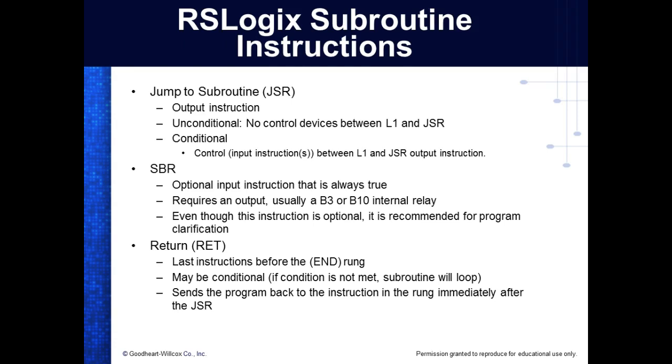Well, if I can't put something up at the very top that says this is an interrupt subroutine or this is a standard subroutine, then I can get really confused real fast. So they recommend that you use these, even though they're optional, so that when I go across those tabs and I see SBR, I know it's a standard subroutine. If I see INT, I know it's an interrupt subroutine, right? Y'all understand? I don't have to figure that out, because if I see an RET at the bottom, that doesn't identify what type of subroutine it is.